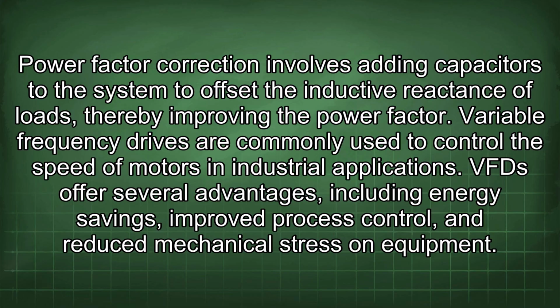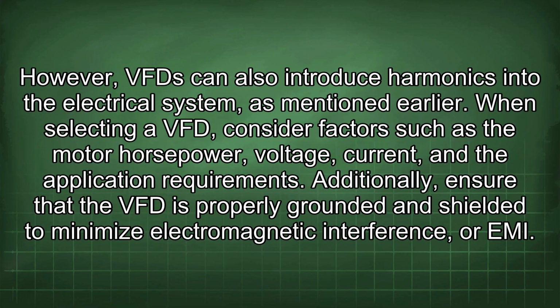Variable frequency drives are commonly used to control the speed of motors in industrial applications. VFDs offer several advantages, including energy savings, improved process control, and reduced mechanical stress on equipment. However, VFDs can also introduce harmonics into the electrical system, as mentioned earlier. When selecting a VFD, consider factors such as the motor horsepower, voltage, current, and the application requirements. Additionally, ensure that the VFD is properly grounded and shielded to minimize electromagnetic interference, or EMI.